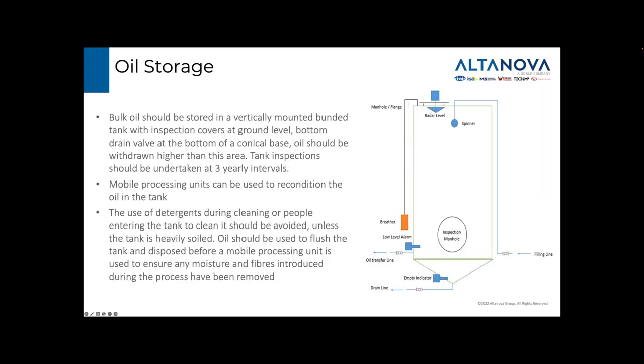Users of large volumes of oil may choose to opt for bulk storage. Providing they are maintained and cleaned every 3 years or so using hot oil flushing and kept in good physical condition, this will keep your oil in better condition than when stored in smaller vessels. There is also less manual handling and forklift operation, making it safer. Cleaning is usually easy as well by using a mobile processing unit to keep the oil and vessel in good condition, just like you would a transformer.